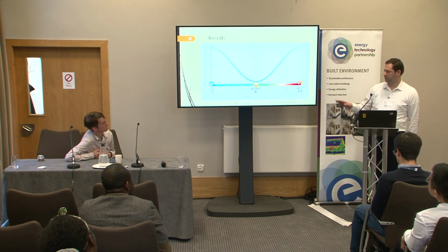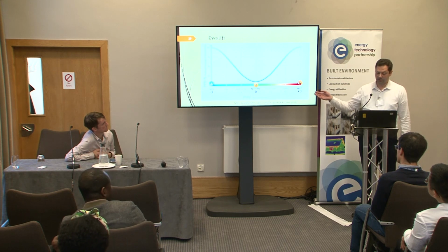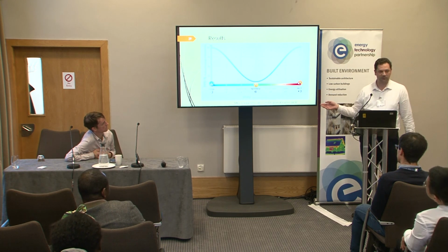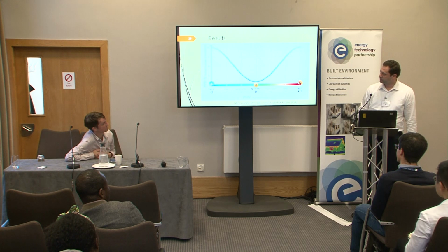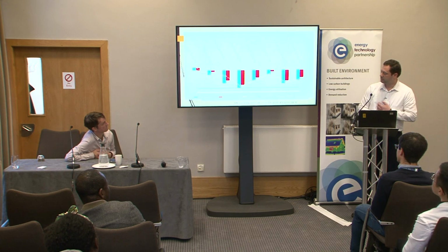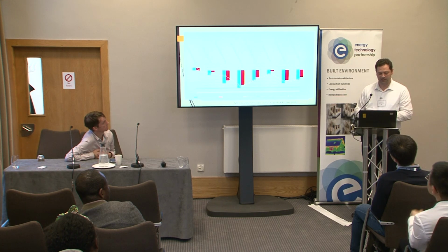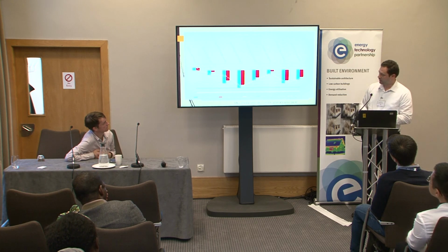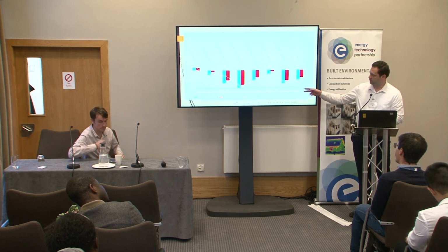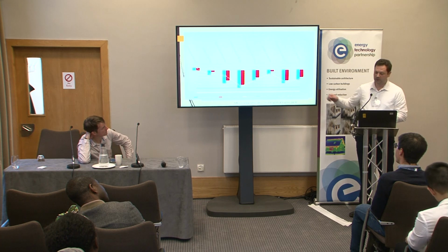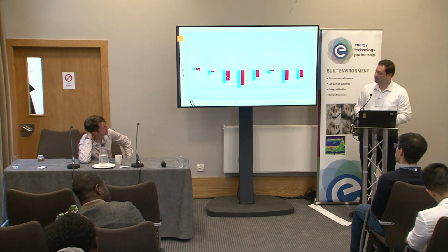We use the predicted mean vote scale for this study. -3 is cold. When you calculate these figures, they're often below -3, which in Scottish terms could be absolutely Baltic, and that might be the relevant term. But I've used Design Builder to simulate what changes could be made, and I have monitored a church in Shoreham by Sea, which is in West Sussex, for a year, and I've got the data. And this is the one day, the 4th of January. The church's comfort level is below cold, despite the heating being on. This was just before the pandemic, so the church was in regular usage.